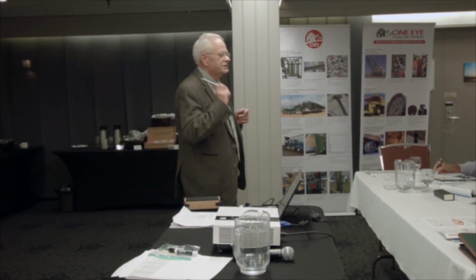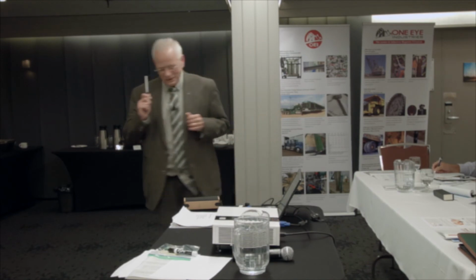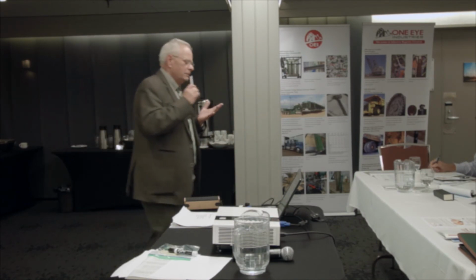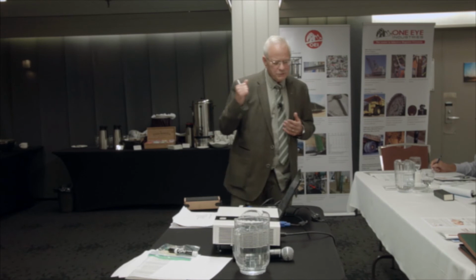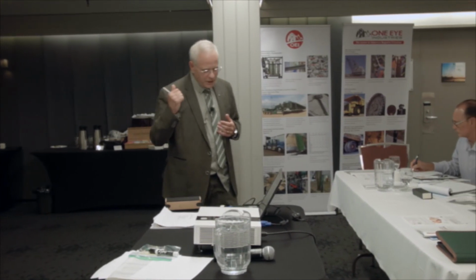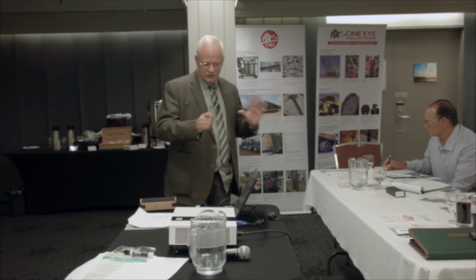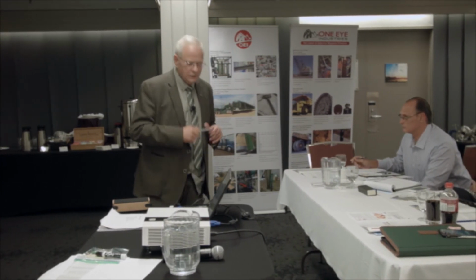As far as warranty, we had a brand new turbine come in. It was a new design. And an insurance claim, insurance agent always told me once, he said, the OEMs manufacture them and the insurance companies pay for them. And that's what happened. We had a brand new design on a gas turbine where they changed the design of the high pressure compressor. 2 weeks in, 7th stage blade on the high pressure compressor failed. You know what the warranty was? They will replace that blade. It cord cobbed the whole unit. So I'll take my chances, you know.